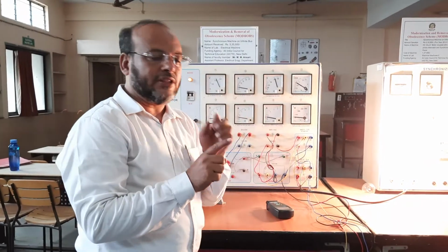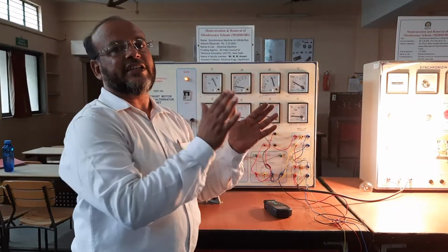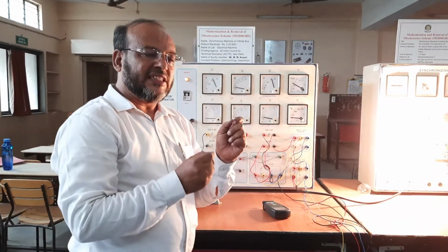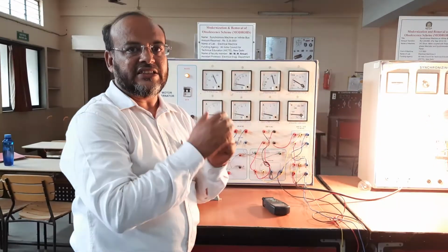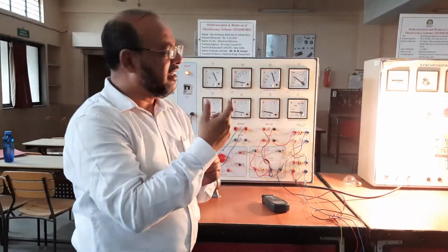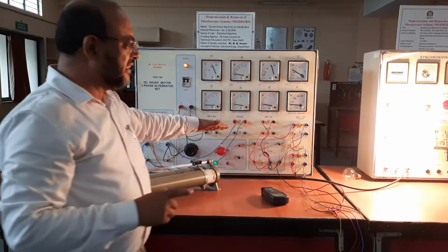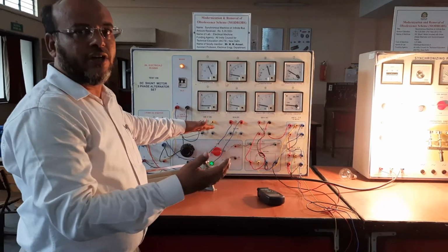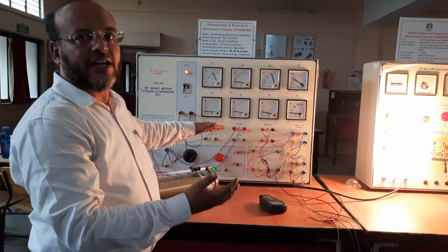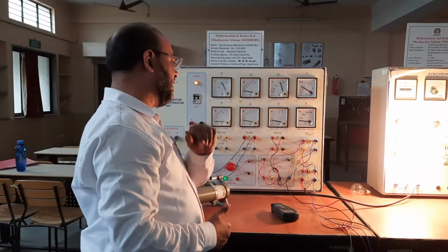This is the main difference between two parallel operated generators and a synchronous machine connected to an infinite bus. If two alternators are working in parallel, a slight change in frequency and voltage is observed. But when the machine is connected to an infinite bus, the bus voltage and frequency remain the same. Only the reactive power and active power delivered by the alternator can be changed, by the excitation and the mechanical input respectively.